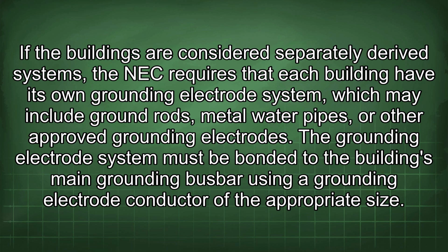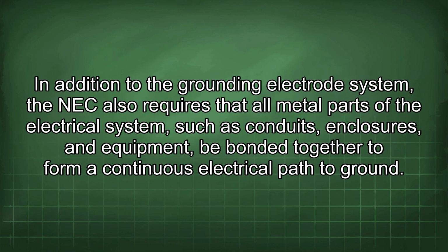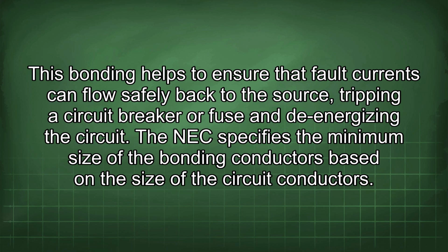The grounding electrode system must be bonded to the building's main grounding busbar using a grounding electrode conductor of the appropriate size. In addition to the grounding electrode system, the NEC also requires that all metal parts of the electrical system, such as conduits, enclosures, and equipment, be bonded together to form a continuous electrical path to ground. This bonding helps to ensure that fault currents can flow safely back to the source, tripping a circuit breaker or fuse and de-energizing the circuit. The NEC specifies the minimum size of the bonding conductors based on the size of the circuit conductors.